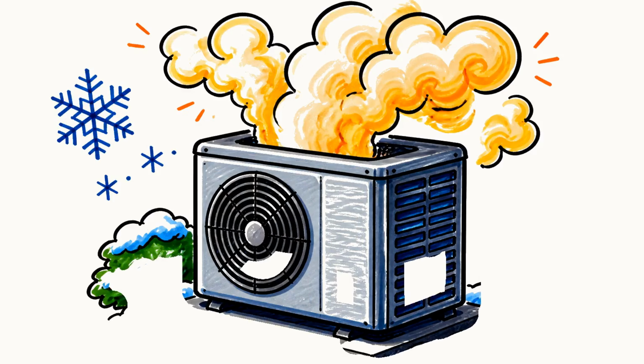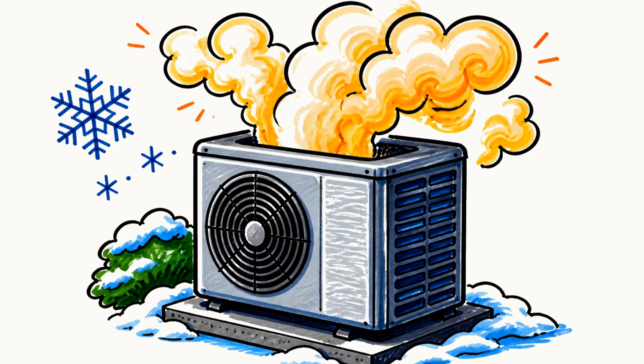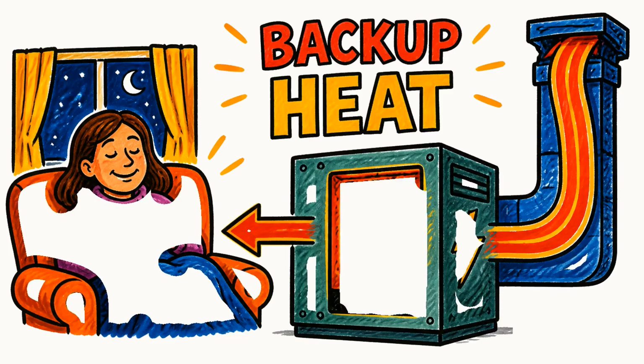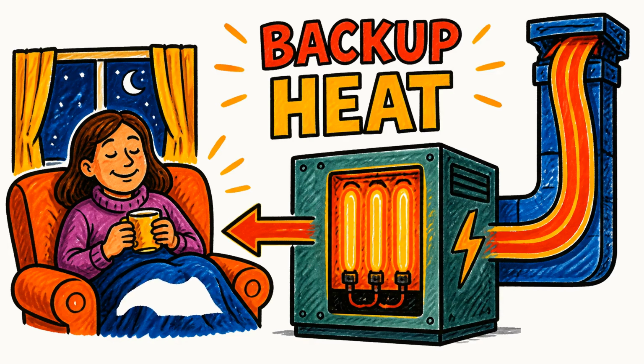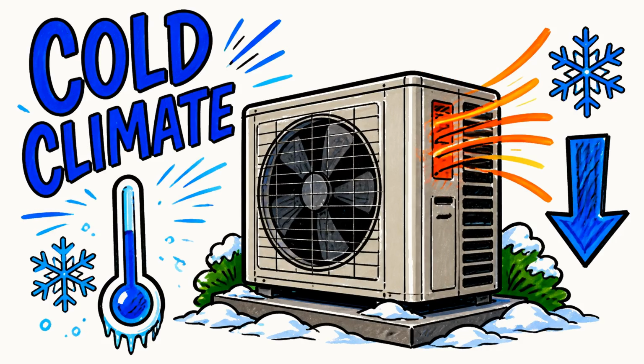That is why you sometimes see steam rolling off a heat pump on a cold day, and it is completely normal. On the truly brutal nights, backup heat, usually electric strips, kicks in automatically so you never feel the gap. Modern cold climate models keep right on working well below freezing.